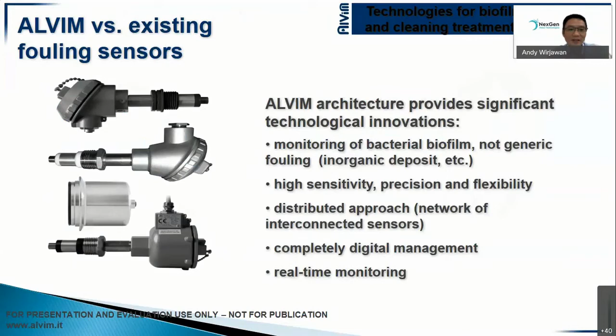The sensor is constructed in different kinds of materials for different applications, from general to sanitary, for the beverage and pharmaceutical industries. Standard would be stainless steel 316, but we can also supply titanium, especially for the desalination industry where the water is seawater. Again, it monitors bacterial biofilm formation. It will not detect generic foulings. It is highly sensitive, which means that at 1%, it will give us a significant reading. It's completely digital, which means it can be connected using standard cabling or wireless. And it's real time, which means it can be read continuously, on a per second, per minute, or even per hour basis, depending on the application. Yeah, next.